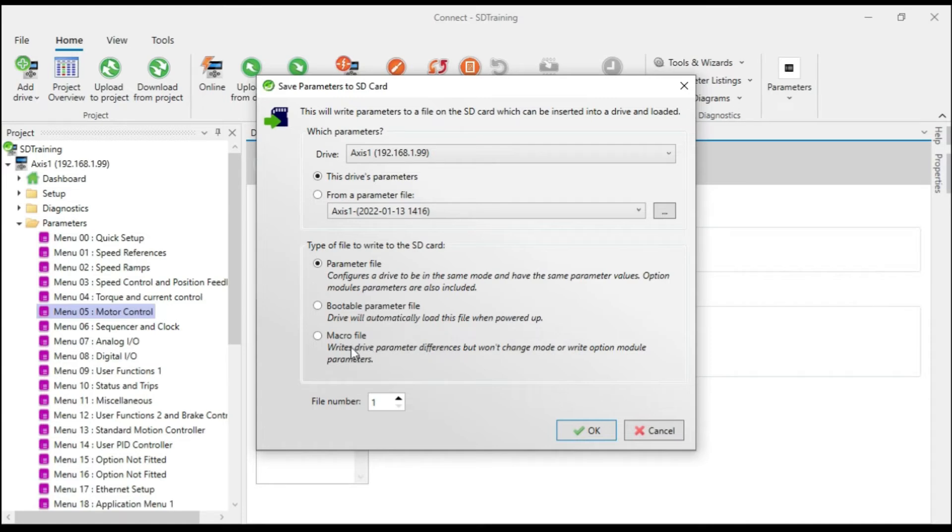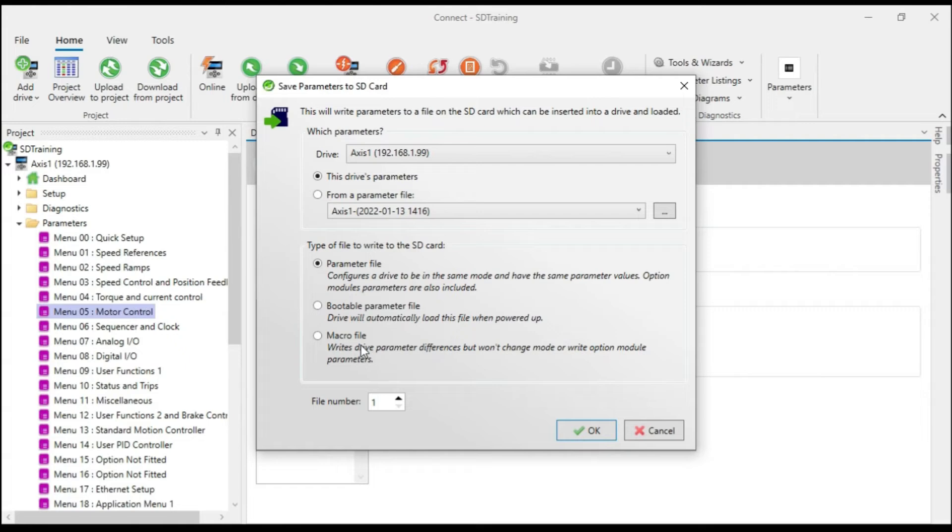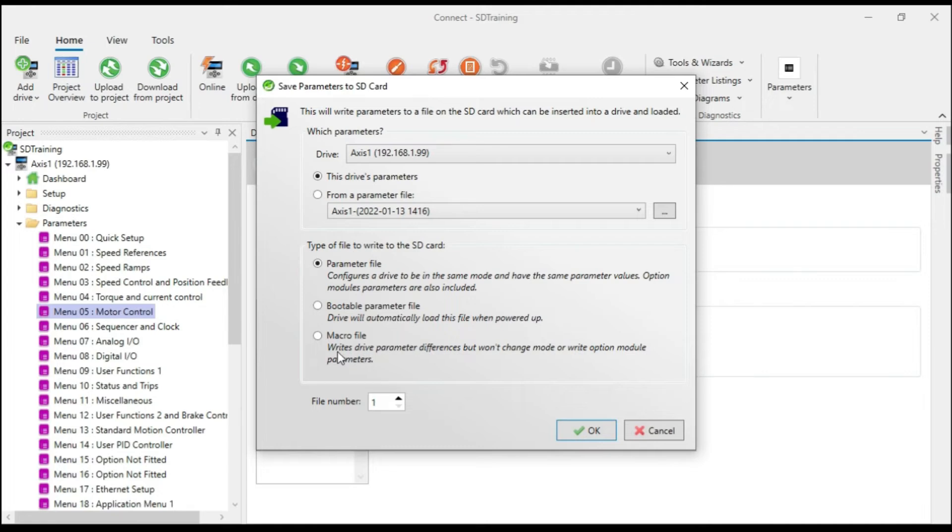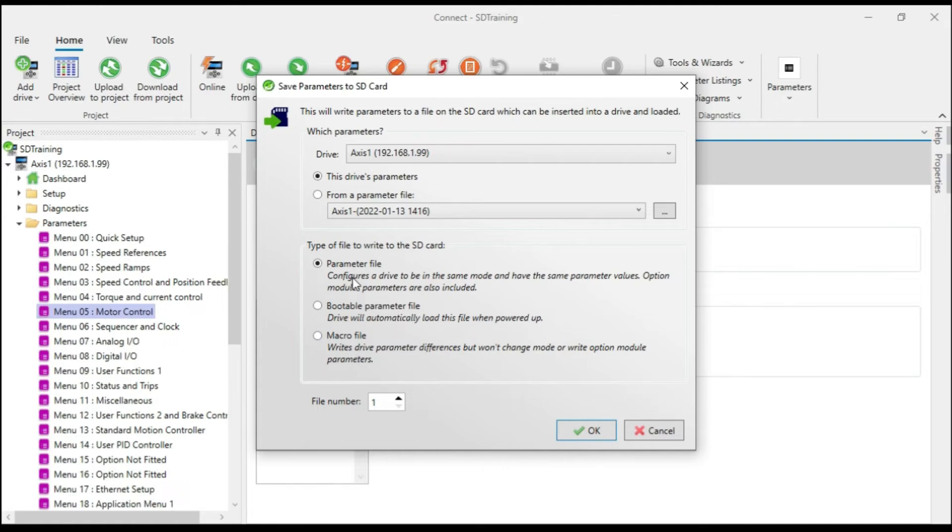The macro file also does not contain any drive specific information. A parameter file will have the drive model number, its operating mode, its voltage rating, where a macro file will not. And a macro file can be used if you have a project with different drive types, different frame sizes, for example, yet you want the drive to have the same functionality as this particular drive does. So that's where a macro file would come in as opposed to a parameter file because the parameter file can only be used with a drive of the same type and operating mode.